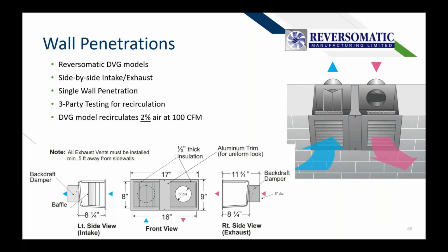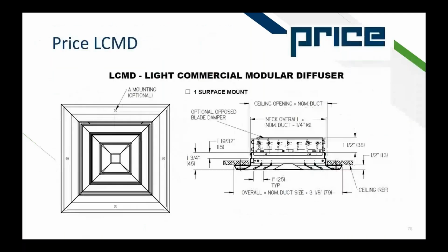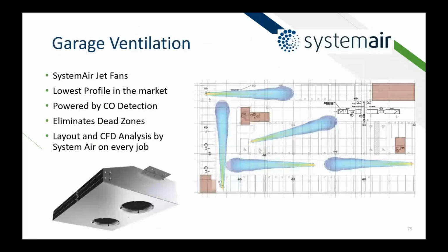How do the jet fans in garages accomplish exhaust? They don't. The question is, how do the jet fans in garages accomplish exhaust requirements? Good question. They do not. They're not intended to accomplish your exhaust requirements. The whole purpose of this is to push air from the intake to the exhaust. Your code requirements for the intake and exhaust are still the exact same. What you'd be doing is just making sure that there are no dead zones by pushing the air around. And you still have CO detection and NO2 detection in the space, based on what you need. Good question.